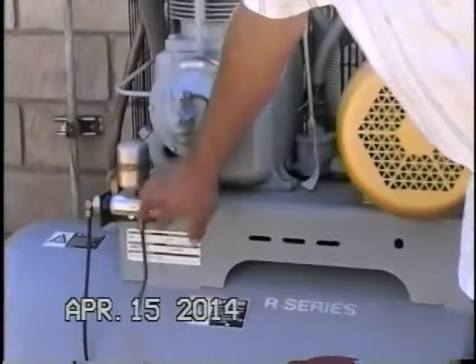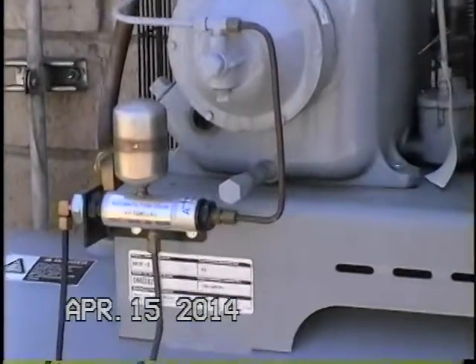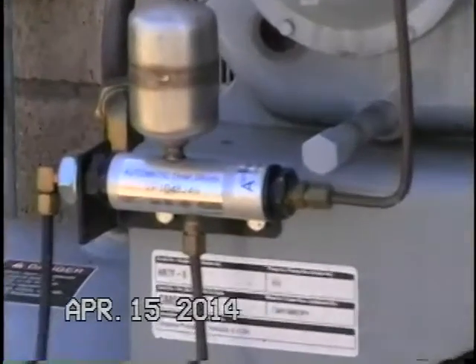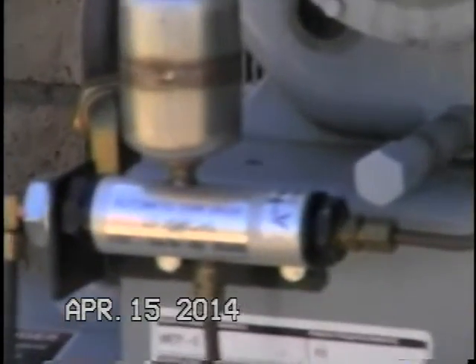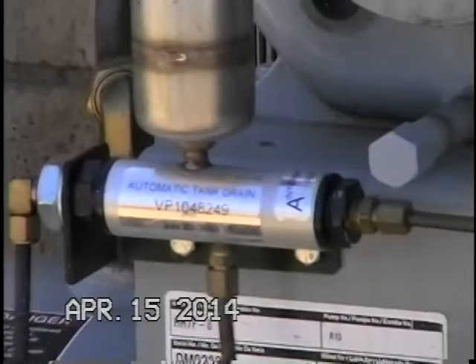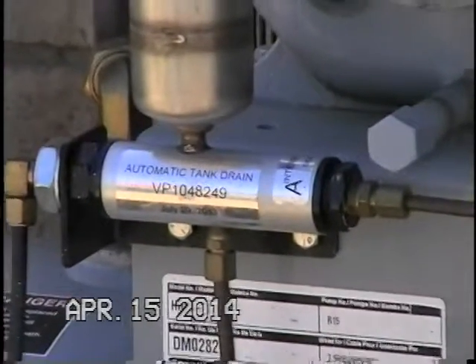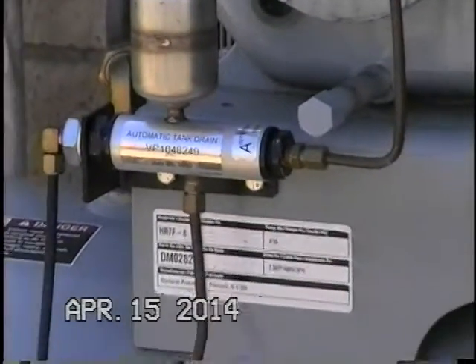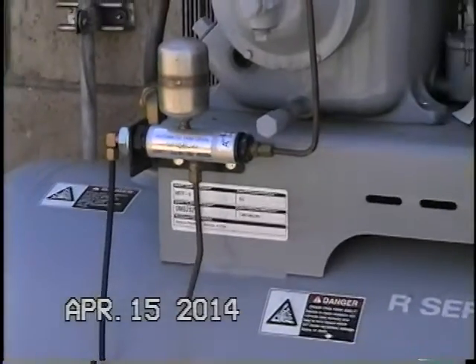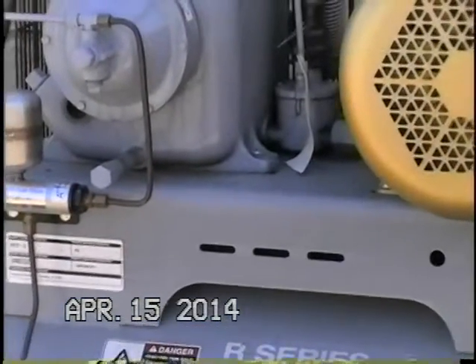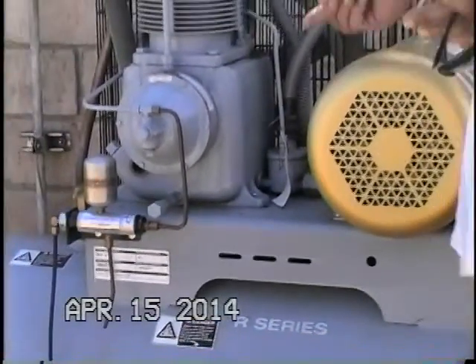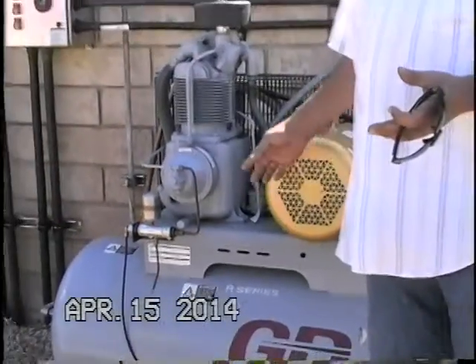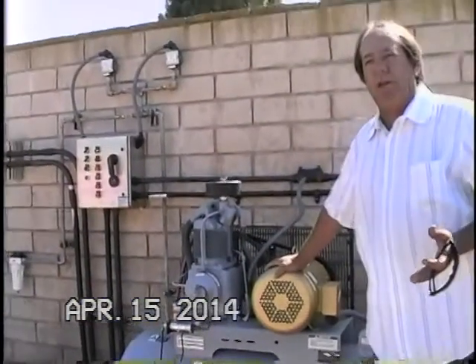The other feature we've got here is your auto drain. I love these little auto drains. They don't get clogged up. They're energized to shut when the compressor comes on, so it's under a loadless start, but it also drains any of the condensate that's in the tank after every cycle of the pump.